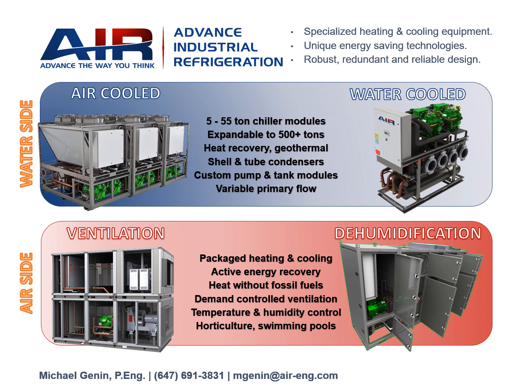Another great question is, is it adding humidity to the air? Now, a lot of passive heat recovery devices, depending on the technology, not all of them, but some of them, can transfer total energy. That means both sensible and latent cooling. So does this active heat recovery, well, it can't transfer latent energy, can it? Well, the answer is yes, it does recover energy from both sensible and latent.